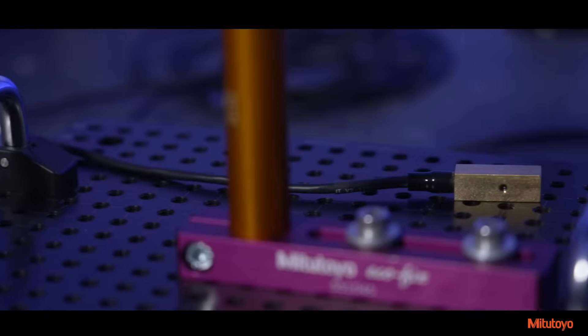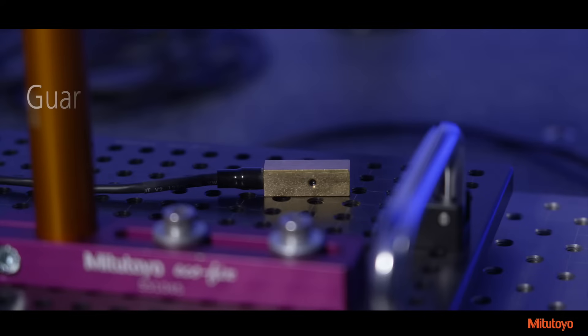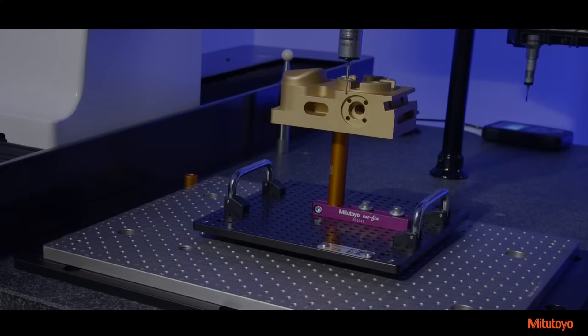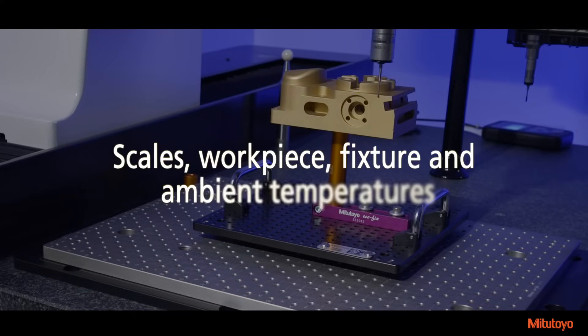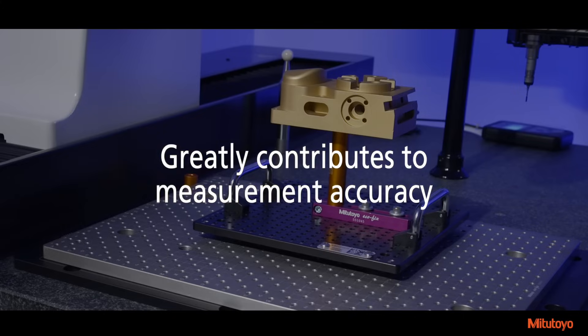The Crysta-Apex V includes state-of-the-art, real-time environmental temperature compensation sensors and guarantees measurement accuracy under an expanded range of temperature conditions, from 16 degrees Celsius to 26 degrees Celsius. The real-time temperature compensation unit measures scales, workpiece, fixture, and ambient temperatures and greatly contributes to measurement accuracy.